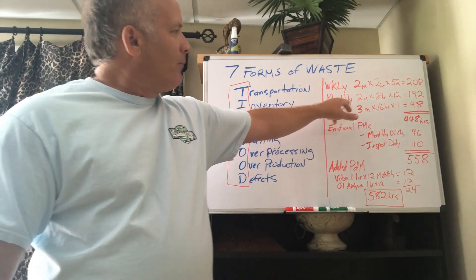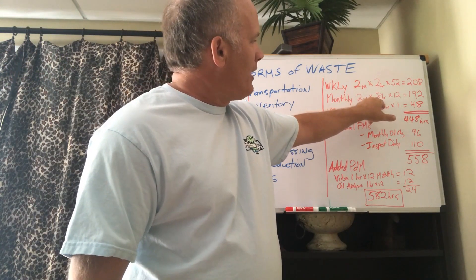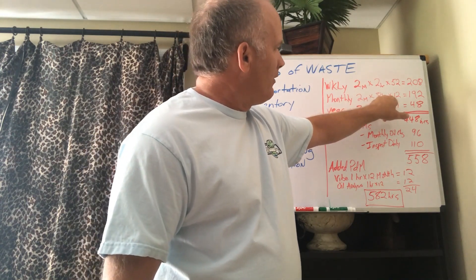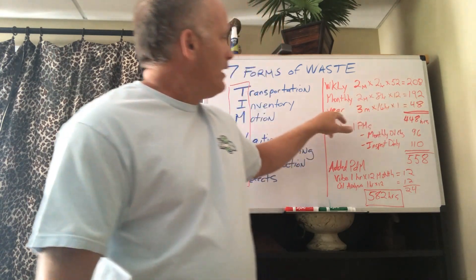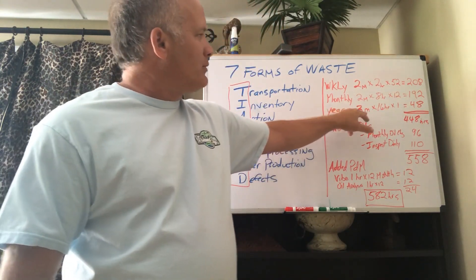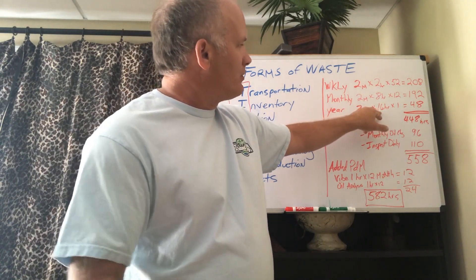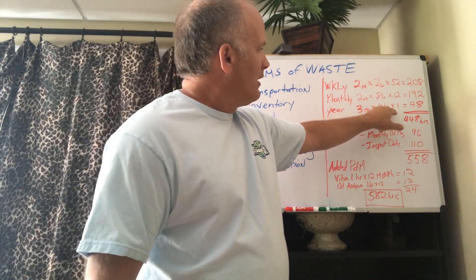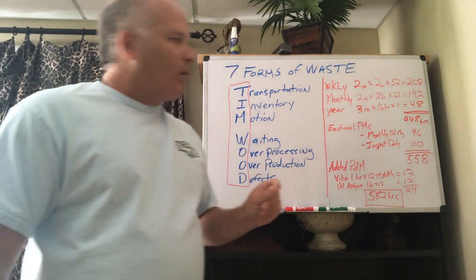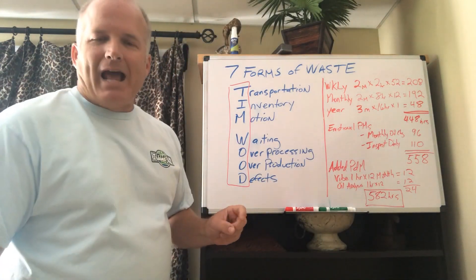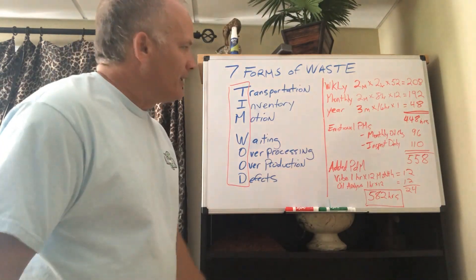Monthly, we had two craftsmen taking the equipment down for eight hours once a month, times 12 — 192 hours. Annual PMs had three people working 16 hours over two shifts, done once a year — 48 hours. So 448 hours total were invested in that asset.